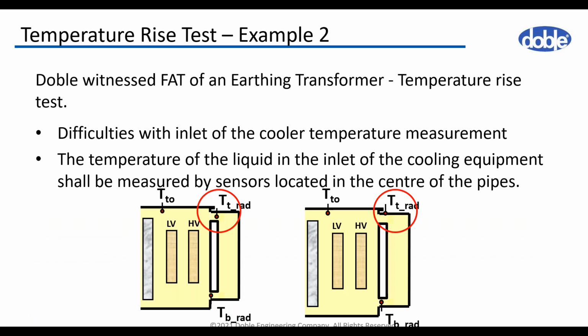So another example: a customer reached out to assist with an FAT on a Earthing Transformer, and during the temperature rise test we found that the manufacturer had difficulties measuring the temperature of the oil getting into the cooler, into the radiator, correctly. The manufacturer applied a sensor on top of the header instead of using a special or dedicated pocket, which places the thermometer inside, in the middle of the oil flow.